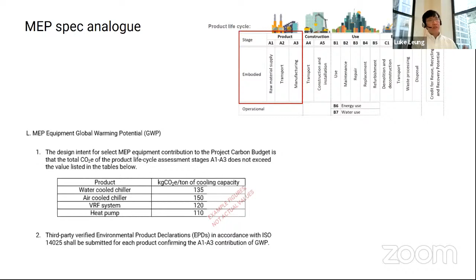This is a sample of what you may see in the carbon, the product stage carbon future. When you specify equipment, you might have to say the product stage A1 to A3, whether it's water cooled chiller, air cooled chiller, VRF, or heat pump, needs to be a certain amount of kilogram carbon equivalent of product stage carbon in our spec.